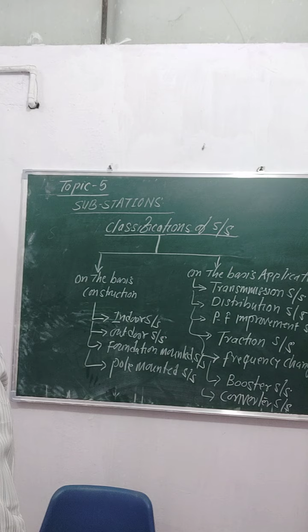Booster substation, again it is a part of traction substation, constructed at a distance of 8 km along the track, and they are maintaining only the voltage in the catenary wire, that is the required voltage of 25 kV. When we run along the conductor, voltage drop takes place. So whatever voltage drop delta V takes place, it is a small voltage that can be added by the booster transformer from the same conductor. Input is taken at 25 kV and then it is stepped down to delta V, and that delta V is again fed to the same wire. So you are maintaining the voltage along the track at 25 kV, and there is no problem in operation of the train.